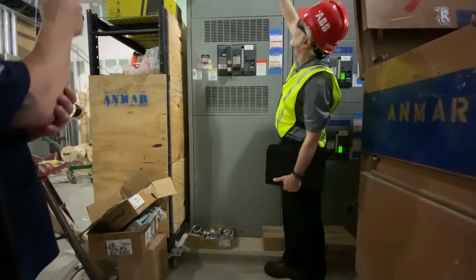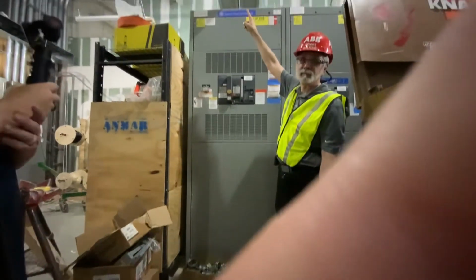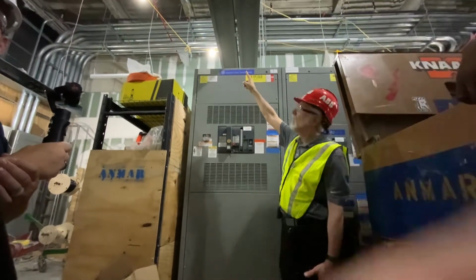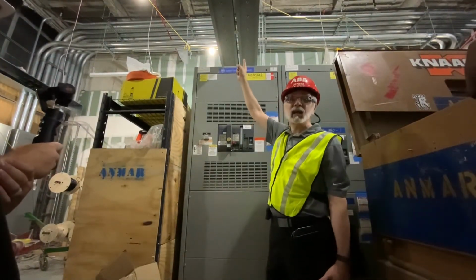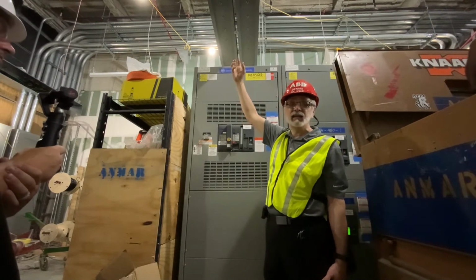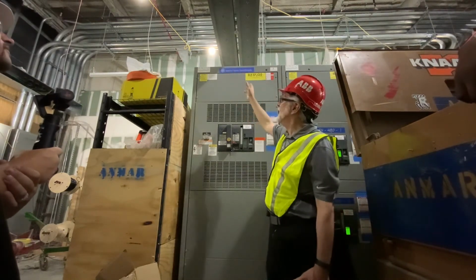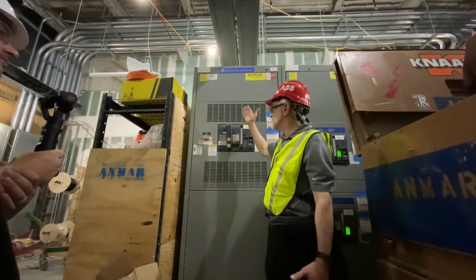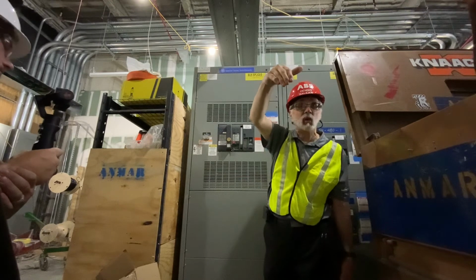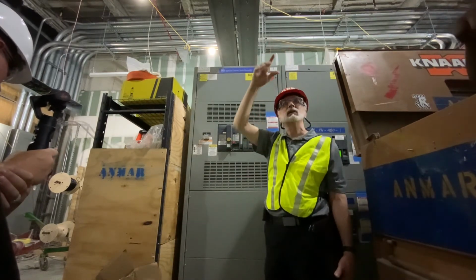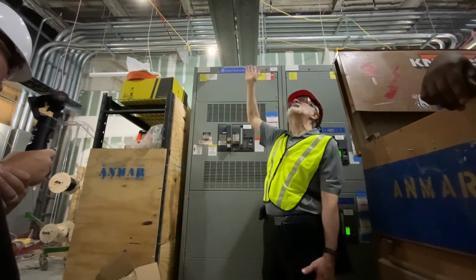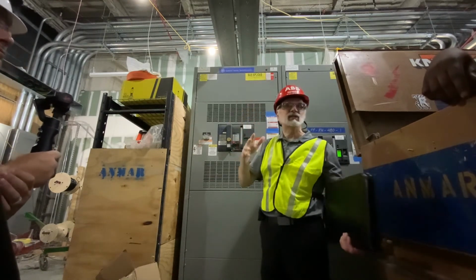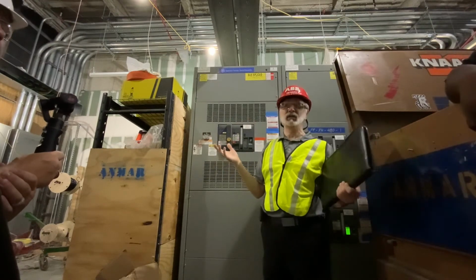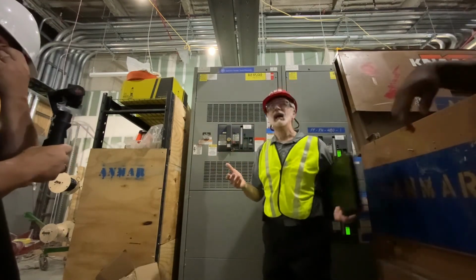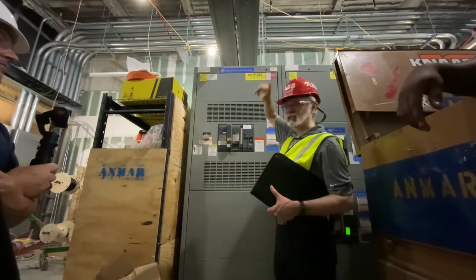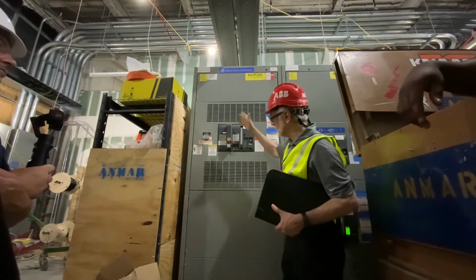If you look up here, you'll notice a piece of busway. This is a set of bus bars housed inside a mechanical enclosure, and rather than using cables to join the tie breaker to the other piece of equipment, we're using bus bars to do that same type of operation. The nice thing about this is it's a lot easier to install, and it's a lot more efficient than pulling like 15 sets of cables, and it's also lighter weight. So we see this very often on split substations.